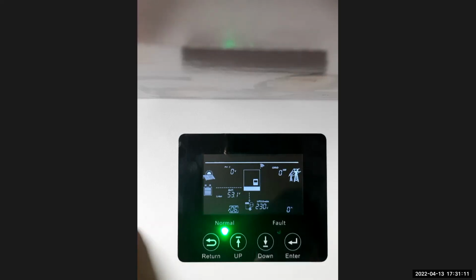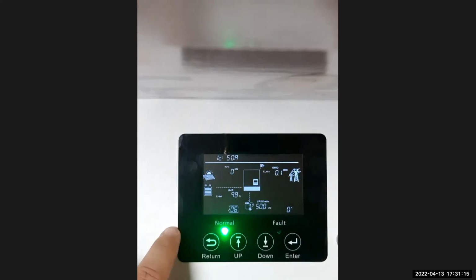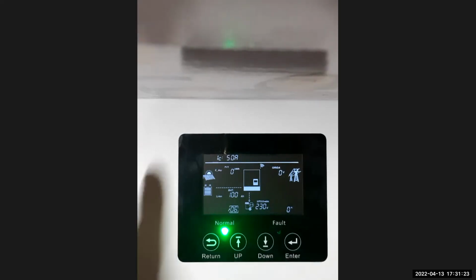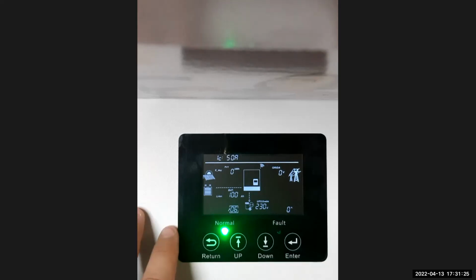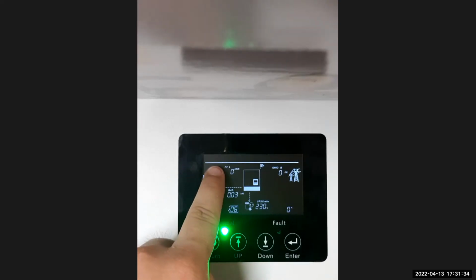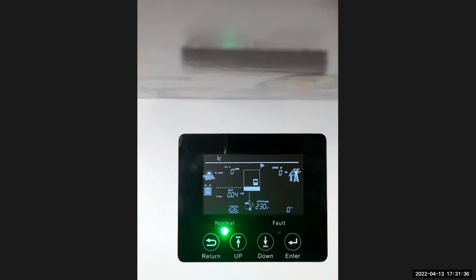So I always like to set my settings on this, even if my battery is communicating, for safety purposes. If something goes wrong with communication, you know you can fall back on the inverter to keep your battery safe without overcharging it by setting this setting. So I've set it to 50. And as you see, if a setting is done, your original setting light will start to flash. Then you know you're done with that setting.